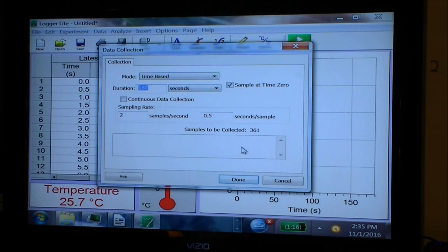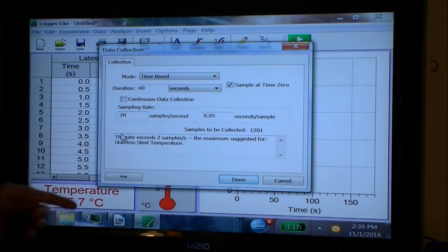And the duration here, suppose we don't want to measure for 180 seconds, suppose we only want to measure for a minute, let's call that 60 seconds. And suppose we didn't want to measure at 2 samples per second, suppose we wanted to measure at 20 samples per second. And we get a little warning note here that says the rate exceeds 2 samples per second, which is the maximum suggested speed for the stainless steel temperature measurements, or the thermometer that we're using. And that's okay, because the force sensor that we're going to be demonstrating later actually goes a lot faster.